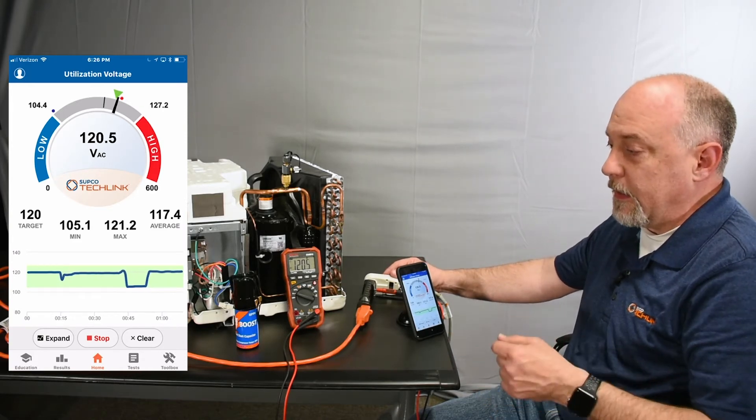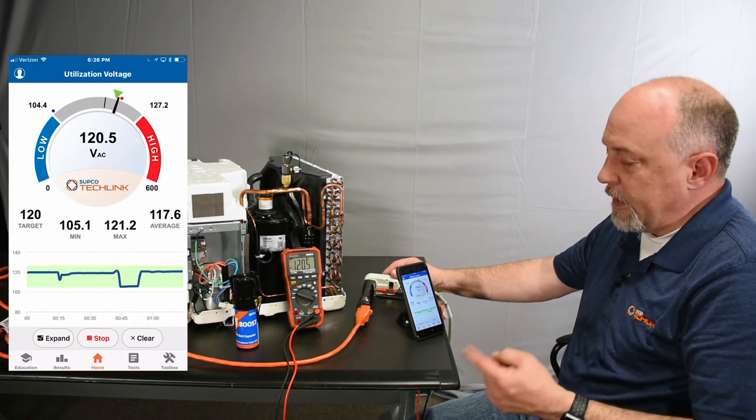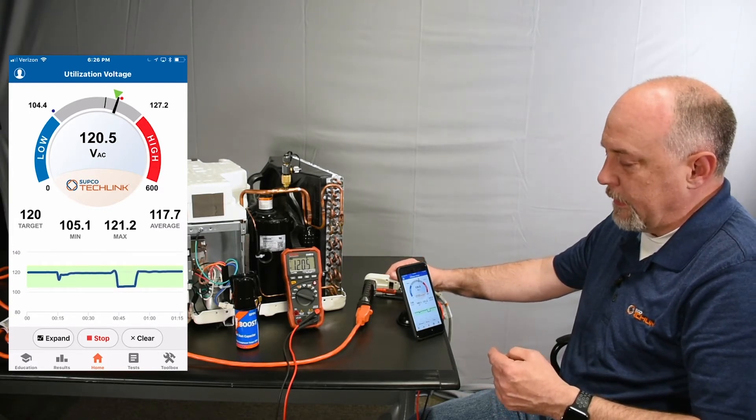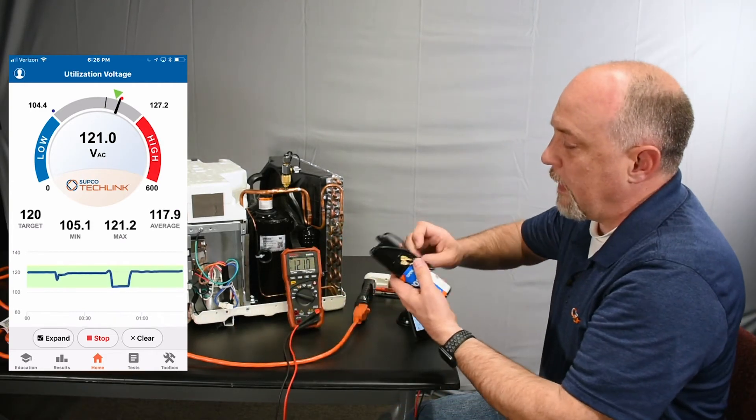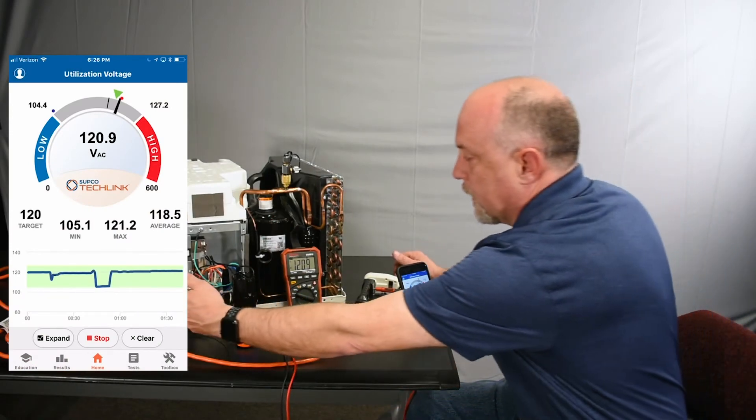I'm going to kill the power and install an original Supco Superboost. We're going to show you the difference in startup. I'll trip the power and take just a second here. We'll install this start device across the common terminal and across the hermetic terminal of the compressor. It hasn't had a lot of time to equalize.